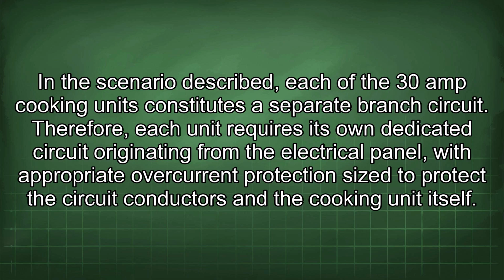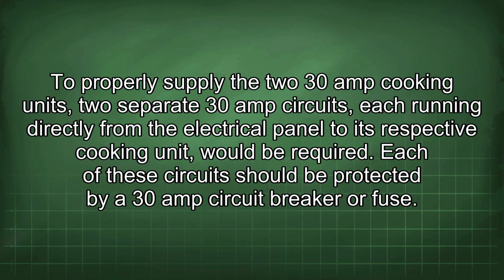In the scenario described, each of the 30-amp cooking units constitutes a separate branch circuit. Therefore, each unit requires its own dedicated circuit originating from the electrical panel, with appropriate overcurrent protection sized to protect the circuit conductors and the cooking unit itself. To properly supply the two 30-amp cooking units, two separate 30-amp circuits, each running directly from the electrical panel to its respective cooking unit, would be required. Each of these circuits should be protected by a 30-amp circuit breaker or fuse.